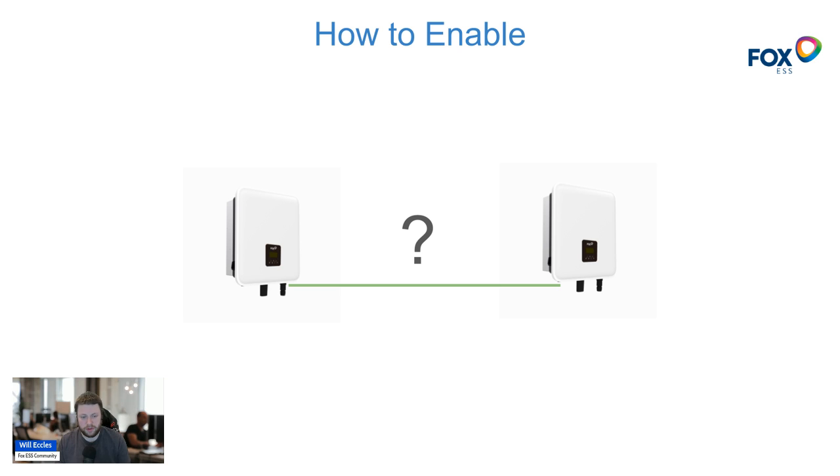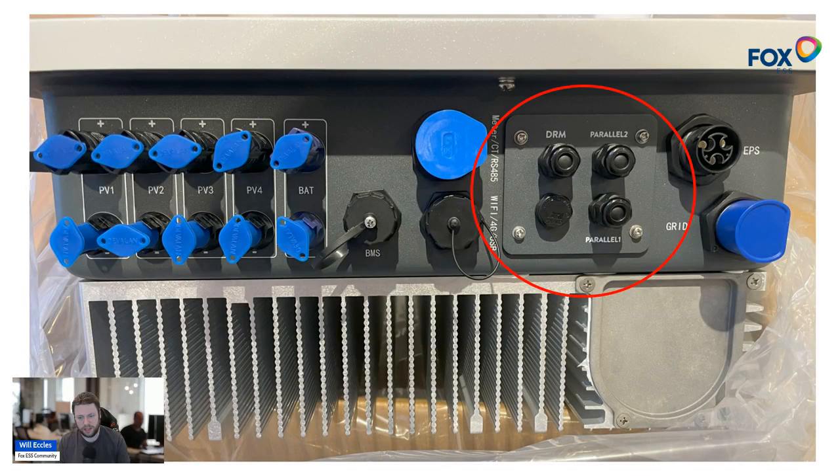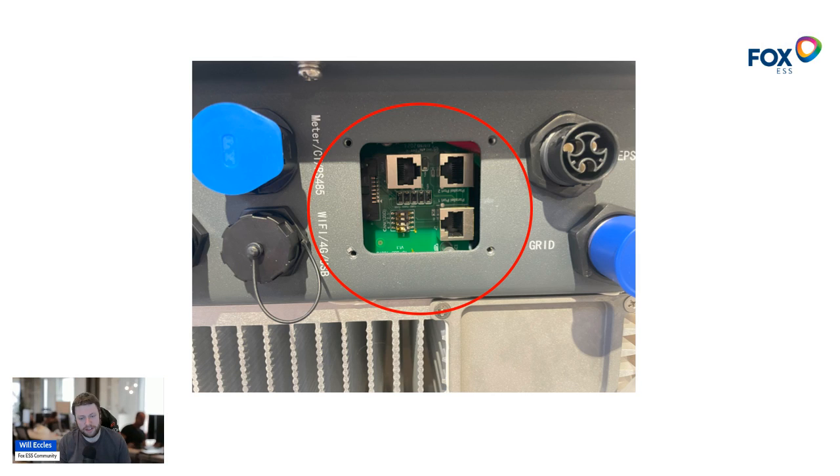To enable two or more inverters to talk to each other and share load, on the K series — and also on the H1 Gen 2 inverter — there's a panel labeled DRM, Parallel 2, and Parallel 1. These are grommets that allow a network cable to pass through. When you remove this panel using the four screws in the corners, you see an area with RJ45-style network ports corresponding to each label: DRM top left, then the parallel ports — Parallel 2 and Parallel 1 — which are the ports we'll be using.